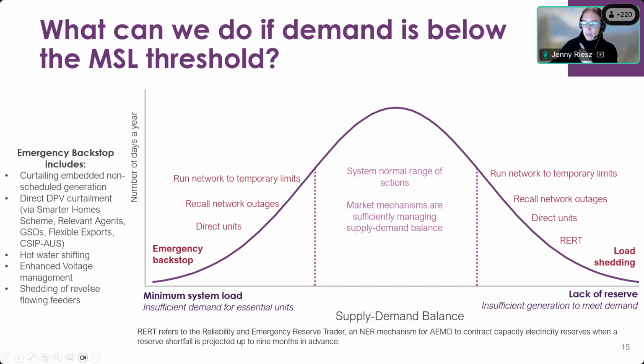That's a mechanism we've brought online in some regions to slightly push up distribution network voltages to deliberately curtail or trip customer PV systems. Obviously not a preferred method, but it has been very effective on several occasions as a last resort for maintaining system security.